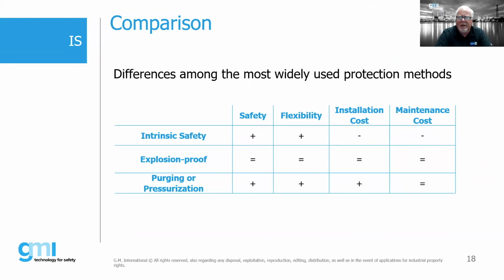And there's more things that can go wrong with flame proof or explosion proof, such as leaving bolts out, scratching the flanges, improper installation of glands. There's a little bit more there that can throw a monkey wrench in and make it not work. Certainly from a flexibility standpoint, with intrinsic safety there's an awful lot of options. Installation cost on intrinsic safety versus, say, flame proof with cabling and glands, there can be significant installation cost and maintenance cost savings.